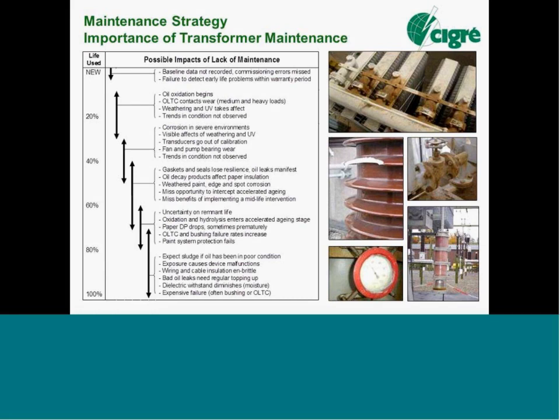If you take the typical distribution transformer, a relatively low value asset compared to a large power transformer, utilities make the conscious decision to do no maintenance, and the maintenance strategy would simply be run to failure, then replace. So you'll see utilities have workshops with stock of new transformers, whole transformers, kiosk transformers, and instead of doing testing or surveillance of these units, they act when the transformer actually fails. So for some devices, no maintenance is a conscious strategy.